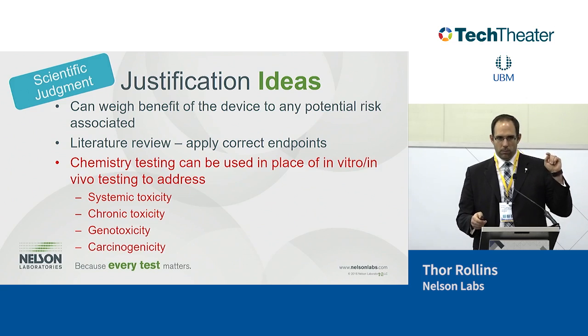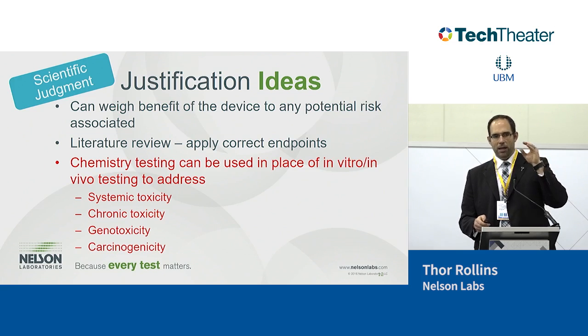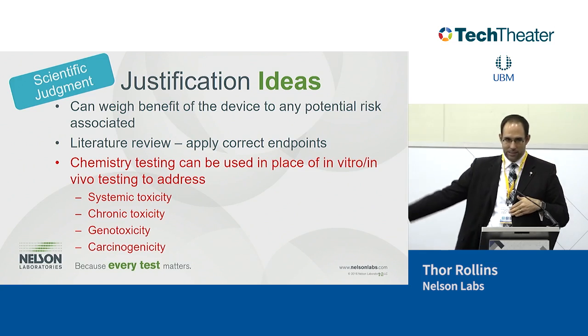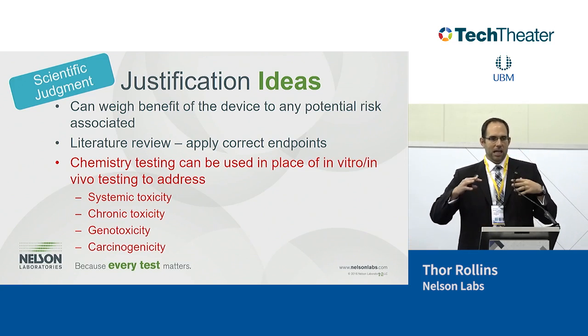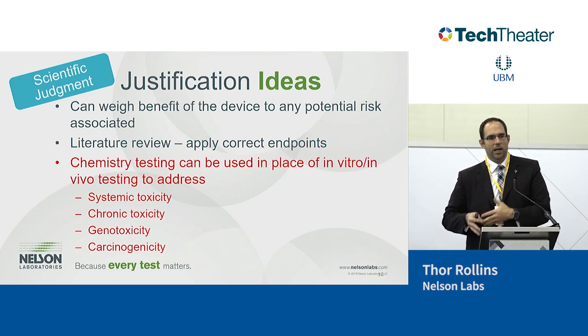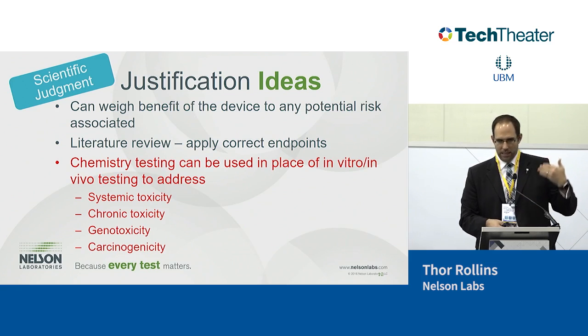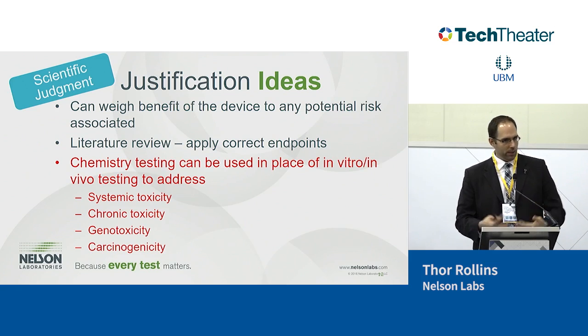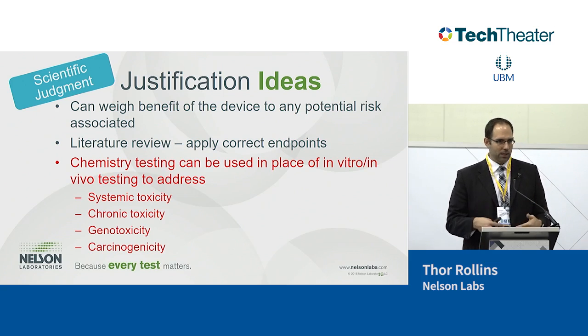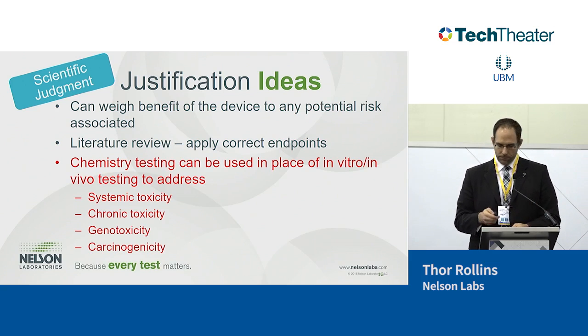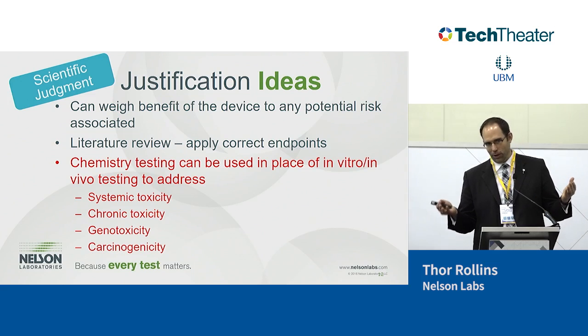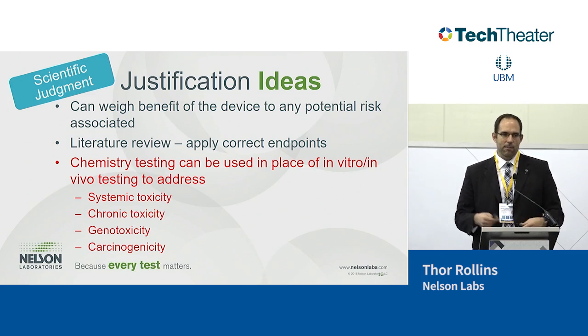I do want to put the idea into your minds: start thinking about chemistry as a synonym for biocompatibility. Okay? Extractables and leachables can help evaluate risks of a device and help eliminate certain endpoints listed down below, where we can then evaluate those endpoints using chemistry and not have to do the tests. That is something the FDA wants us to look at, something they put in their guidance document, something they've stressed to us on the phone, something that's been very successful. And by the way, it happens to be cheaper and quicker than some of these animal tests, and gets better information.